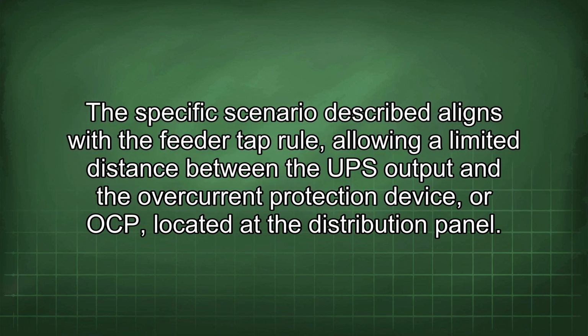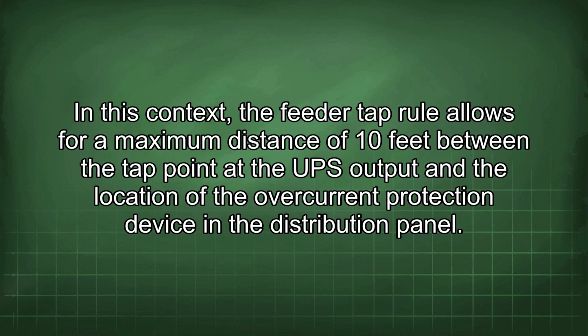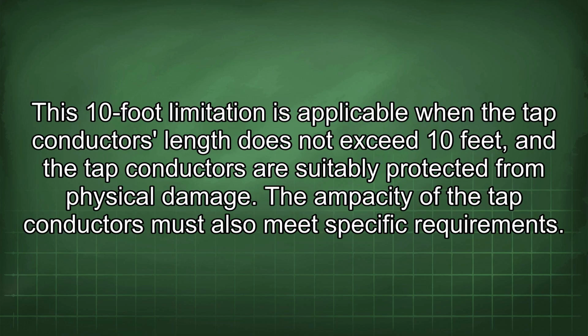The specific scenario described aligns with the feeder tap rule, allowing a limited distance between the UPS output and the overcurrent protection device, or OCP, located at the distribution panel. In this context, the feeder tap rule allows for a maximum distance of 10 feet between the tap point at the UPS output and the location of the overcurrent protection device in the distribution panel. This 10-foot limitation is applicable when the tap conductor's length does not exceed 10 feet and the tap conductors are suitably protected from physical damage.